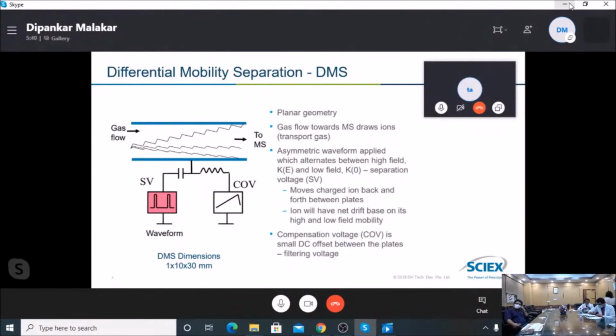There is another voltage called compensation voltage, or COV shortly. This is a small DC offset between the plates. Since ions move towards the wall of the cell, the compensation voltage adjusts and brings the ions to the proper trajectory, so that the ions come out from the cell in a proper trajectory. So this is called compensation voltage, a small DC offset between the plates, or I would say filtering voltage. Two different voltages are applied.